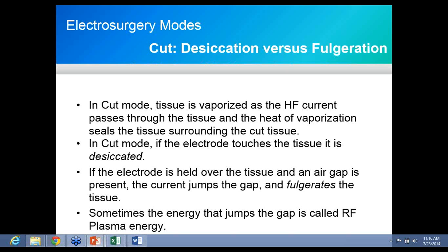So how do you differentiate desiccation versus fulguration? In desiccation, the electrode, the pen tip, actually touches the tissue. If the electrode is held over the tissue and an air gap is present, then current jumps that gap and fulguration occurs. Sometimes the energy that jumps the gap is called RF plasma energy by physicists. And if you happen to weld, this is the same process that occurs when you are using a high voltage electrical welder and the current is jumping the gap. It's known as plasma welding.